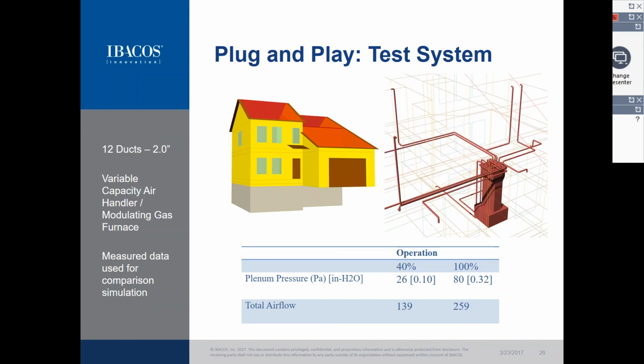So the system that was installed, again, was PVC ducts. We had a total of 12 ducts for this house, and we were able to get by with 2-inch PVC pipe. Partly that was because, again, this house is such a low load that 2-inch ducts were able to satisfy those loads and that airflow. 2 inches probably isn't realistic for a more production scale type of house.